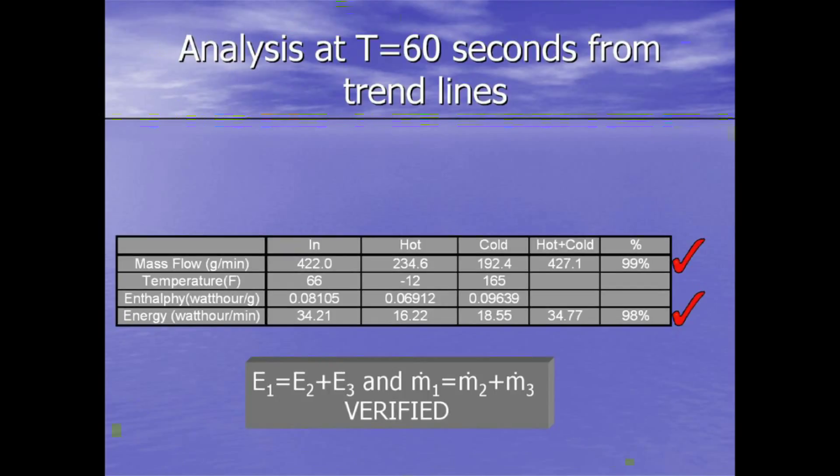Sticking that into an analysis table at the time equals 60 seconds and running the numbers where I took the mass flow in versus hot and cold and see how they compare, the in versus hot plus the cold, the numbers were within 99 percent. I thought that was very good, and the same thing when I took the temperatures and looked up in the gas table the enthalpy. It gave it to me in BTUs per pound, so I had to convert it to watt hours per gram.